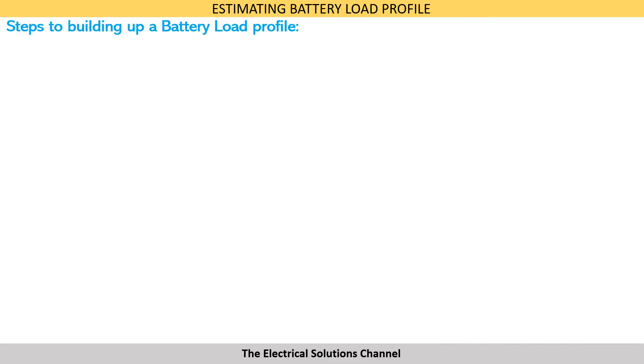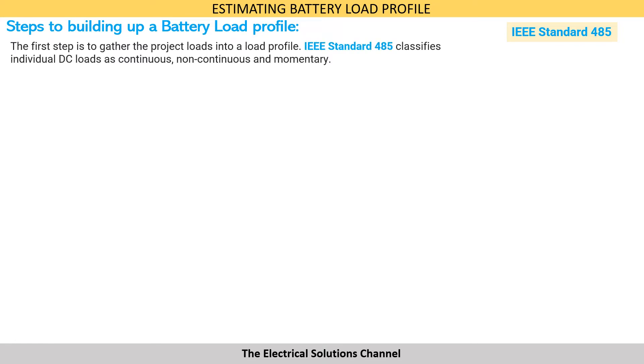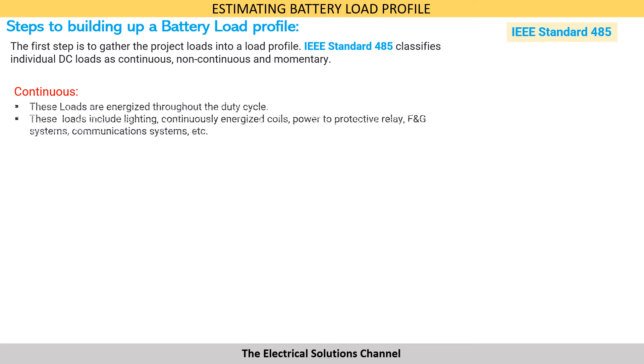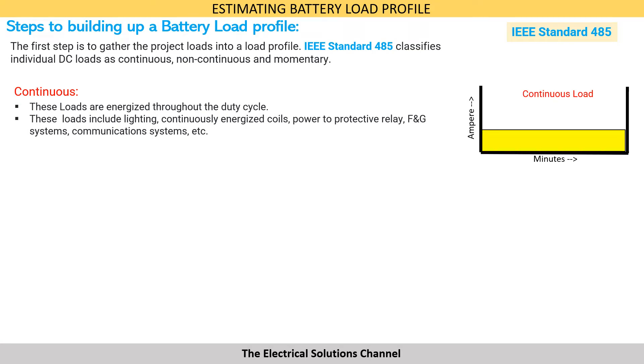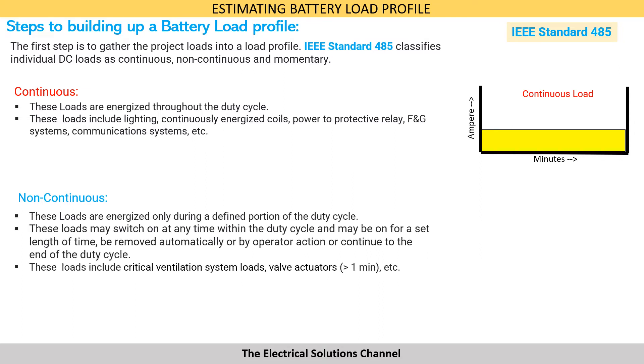Let us now understand the steps for building a battery load profile. The first step is to gather the project loads into a load profile. IEEE 485 classifies individual DC loads as continuous, non-continuous, and momentary. Continuous loads are those which are energized throughout the duty cycle — these include lighting, continuously energized coils, power to protective relays, F&G systems, and communication systems.